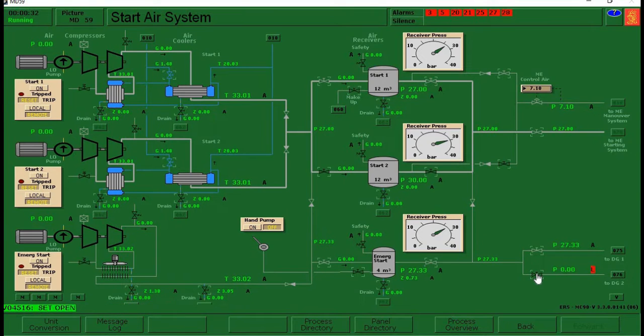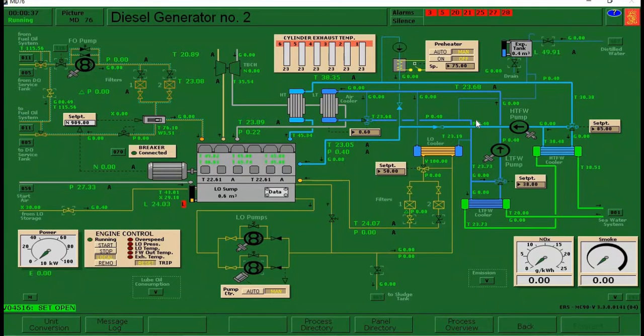We should open this supply valve, air supply valve towards our diesel generator 2. Let's go back to our DG2. And we open this valve here from our DO service tanks. And we need to turn on the preheater and set it to auto. So after that, we close this makeup valve, because if we don't, there will be a high level alarm here in our lube oil sump level. Okay, so let's turn it off. Then pump control in automatic.